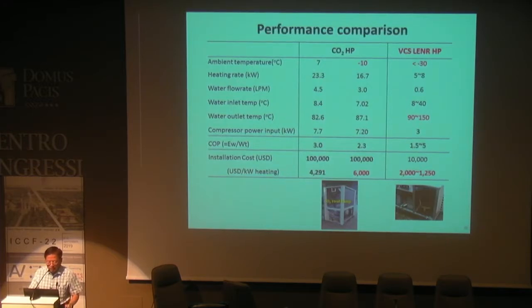if I do some comparison of the two machines, the CO2 heat pump, then in terms of the installation cost per kilowatt of heating with a minus 10 degree environment in a north latitude area, the cost is $6,000, because this machine costs about $100,000. We are in business. This is the real price. And with the VCS heat pump, as I explained, it can run even at minus 30 degree ambient temperature. The cost is about 1,000 to 2,000 per kilowatt. It's about 3 or 4 times less than the CO2 heat pump. This means even though we didn't know what happened, the commercial product can go ahead.